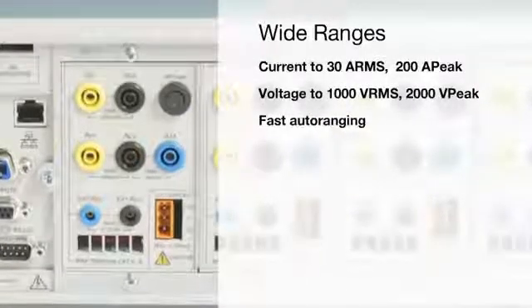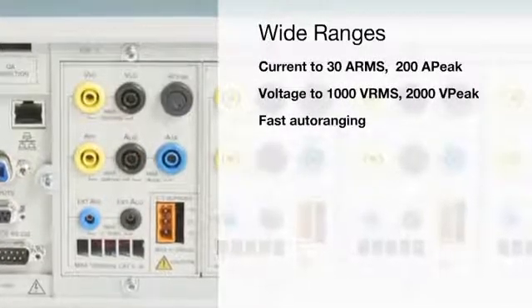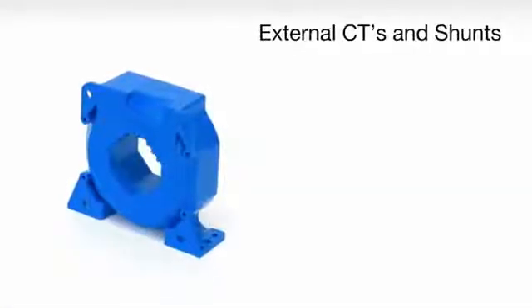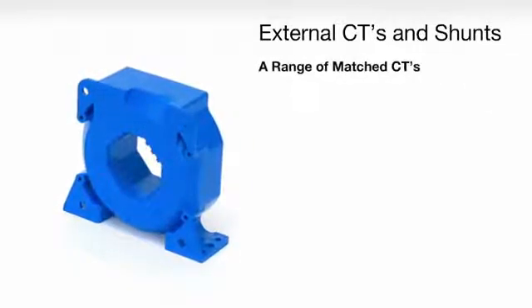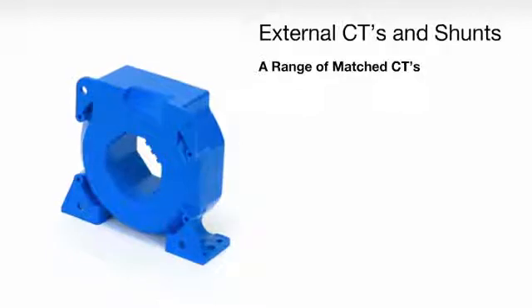Fast auto-ranging minimizes data gaps during wide current swings. For even higher currents, the PA-4000 supports external shunts or current transducers. A range of matched current transducers is available from Tektronix.